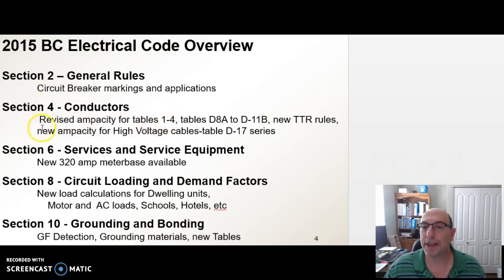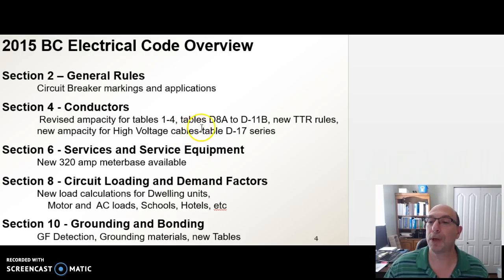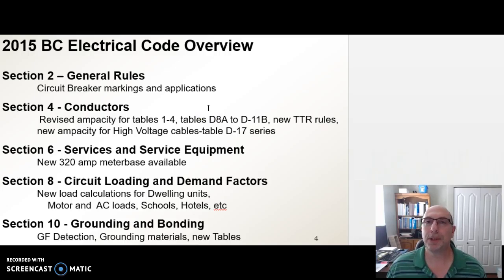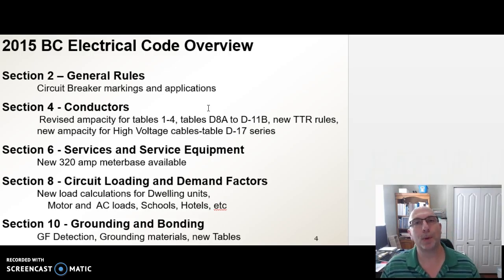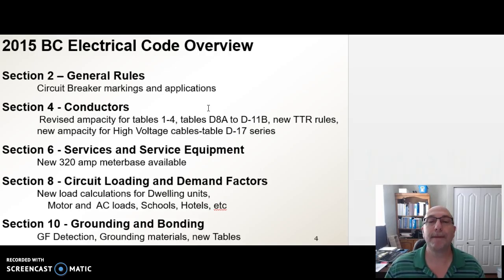There are big changes in Section 4. We have some revised ampacities for Tables 1 through 4 — be careful on that. Regarding Tables D8A and D11B: for those installing conductors 1-0 or larger underground, in the old days you would have to go to Appendix B to look for the cable or conduit configuration, then go to Appendix D to find your ampacities — there was a lot of confusion. Now, all you have to do is go to Appendix D8A and D11B, look for your cable configuration, flip the page, look for your ampacities. Done. It's really streamlined.